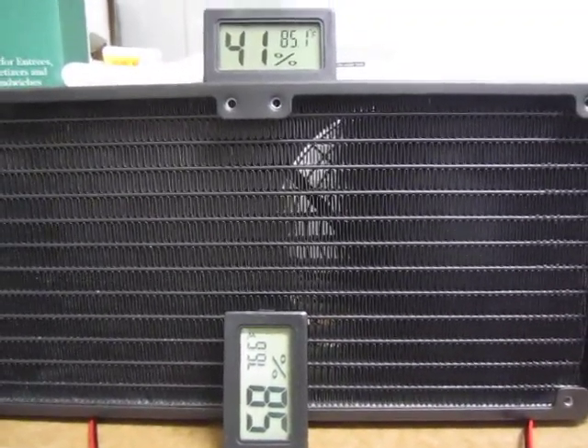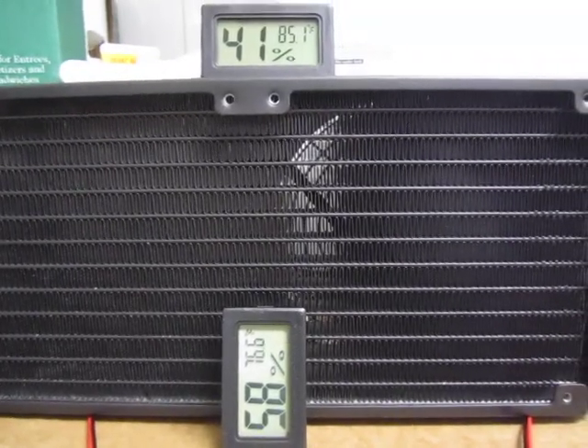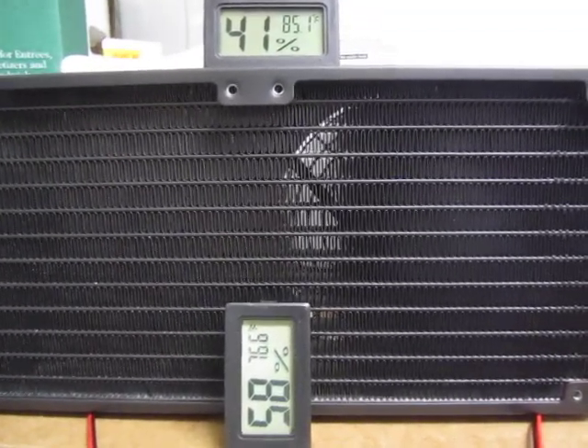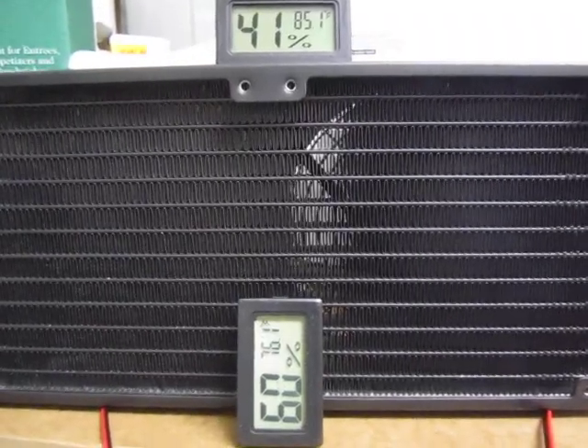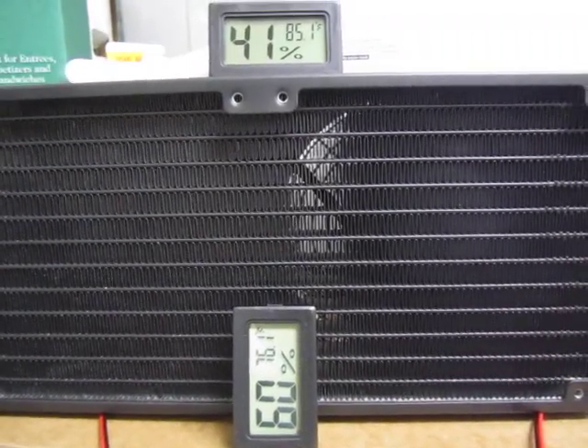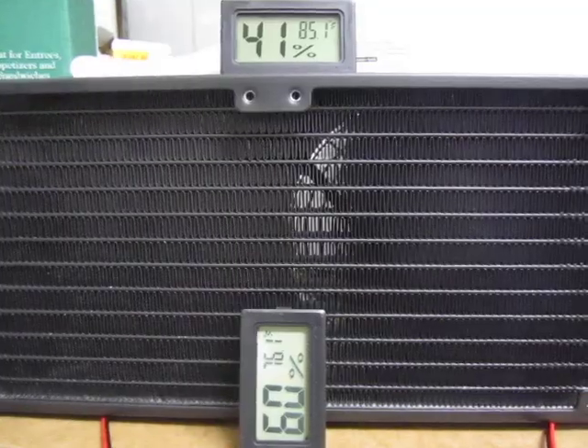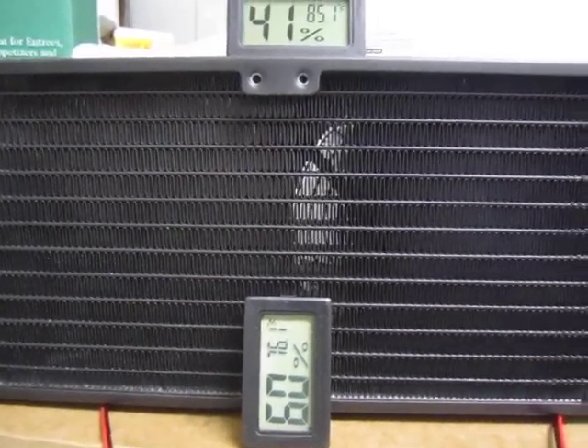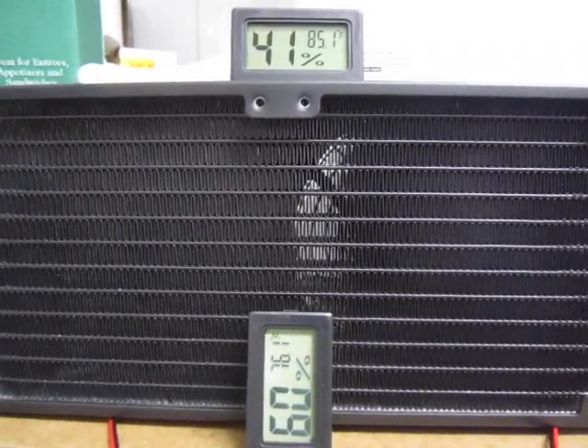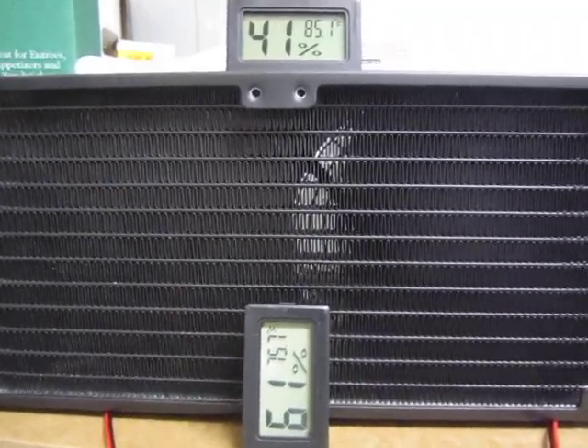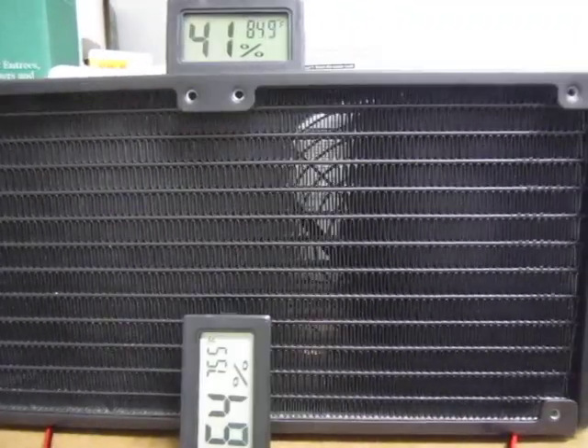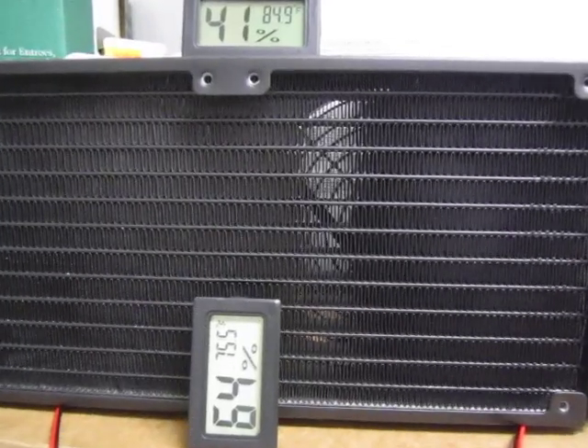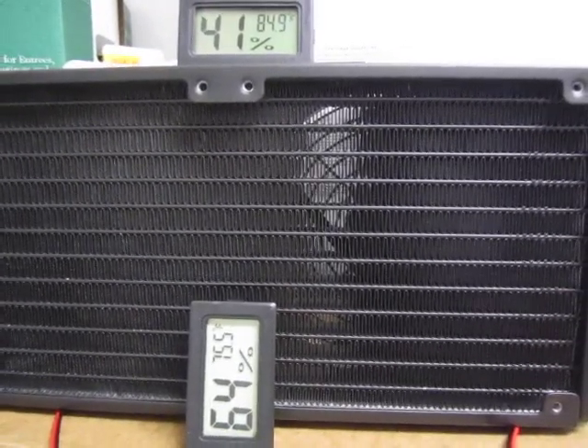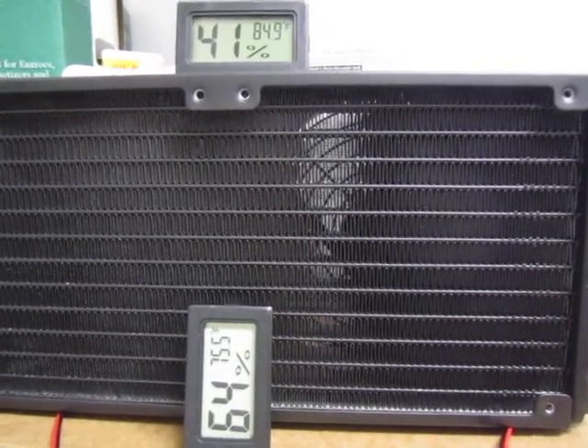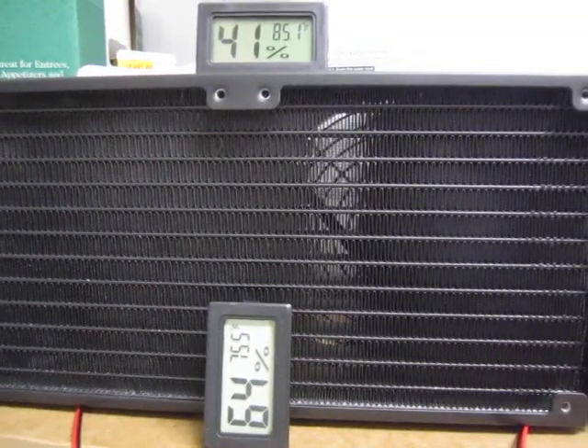Basically you're going to get a lot more bang for your buck trying to cool down something relatively hot rather than something at room temperature—you won't be able to make as much of an impact there. Just like that, we're already down to 76 degrees at the front, and now we're down to 75.7. Another minute or so has gone by, and now we're at about 75.5 degrees at the front, 64% humidity.